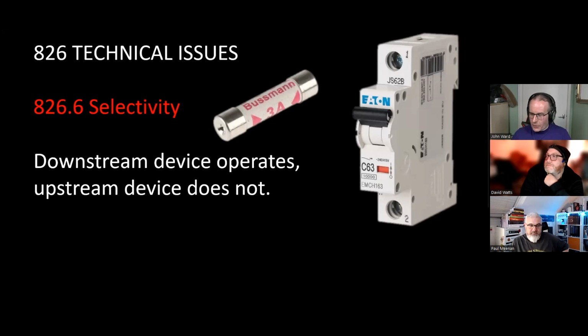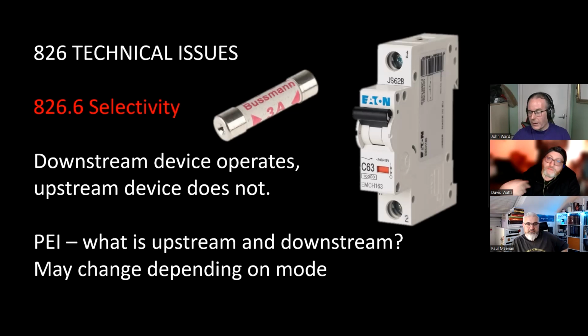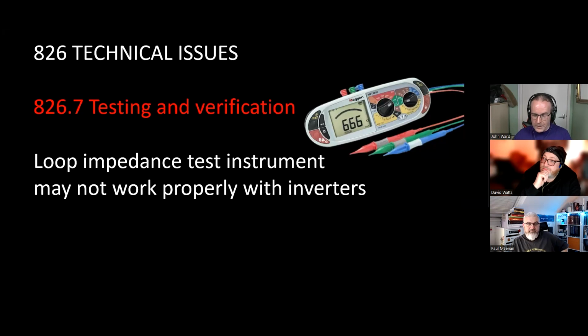Selectivity, same concept as with anything else. If you're going to have more than one protective device, you want to make sure that the downstream device operates first, such as your 3-amp fuse there, and the upstream device does not. You don't want to be taking out whole chunks of installation because of a small fault. And again, think carefully about where the actual upstream and downstream are, because that can change depending on where your supply is coming from. So there's a nice pile of complexity.